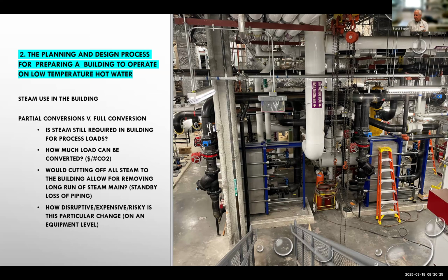When building conversions can be done as an alternative to replacing steam equipment, this makes the most of your investment. If you replace functional, good heating equipment early, you're losing its remaining value. And this is where partial conversions can come into play. For example, if you are going to convert a building in 5 years, but you need a new air handling unit now, you want to make it run on low temperature hot water now and let the building systems catch up later. Even if you're using a higher temperature hot water system now, size the coil so it can operate at the future lower temperature.